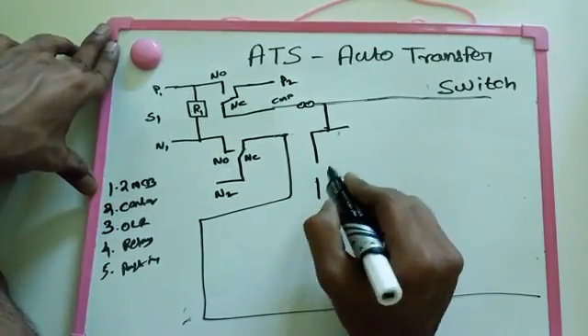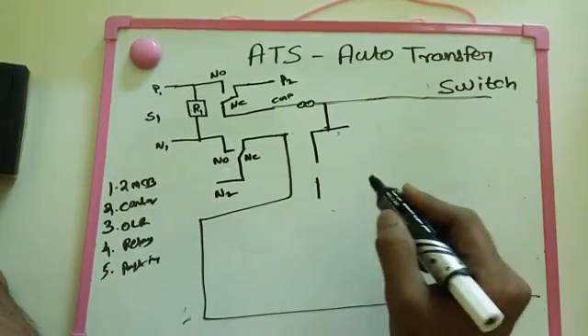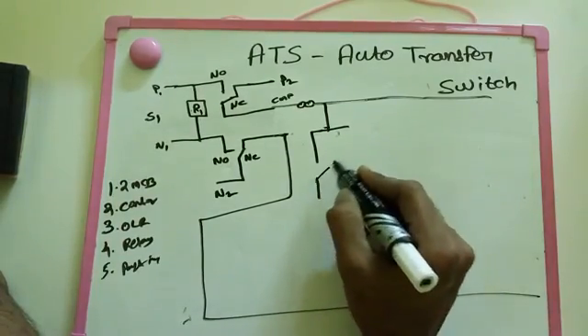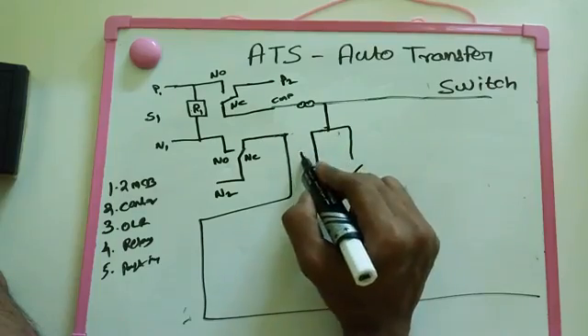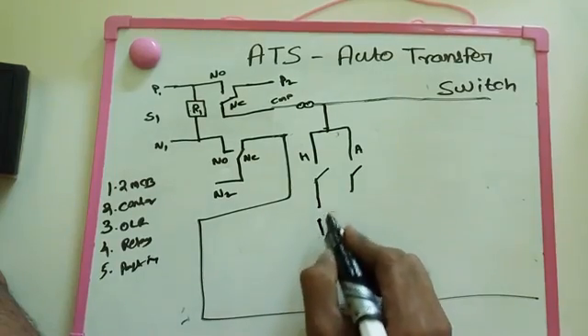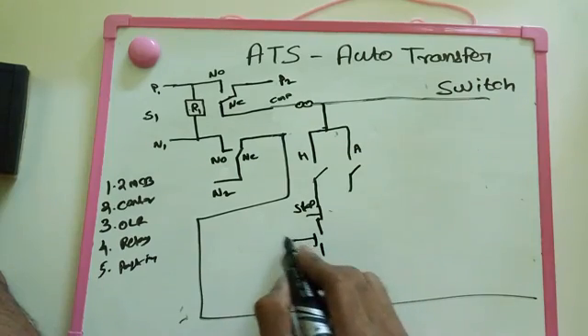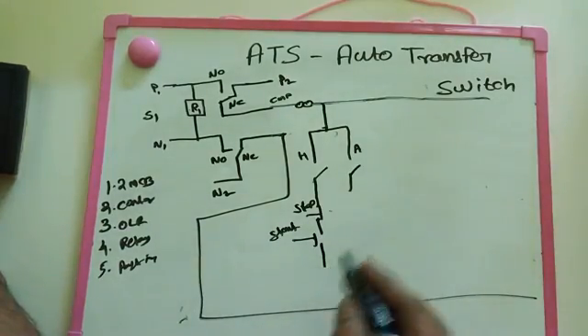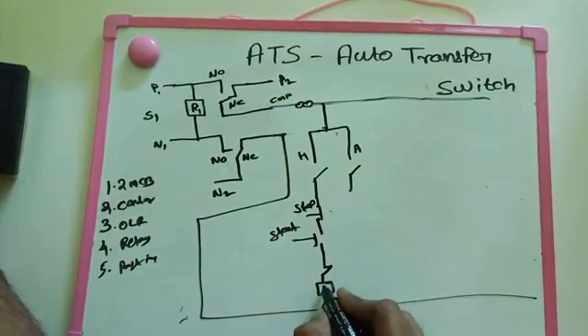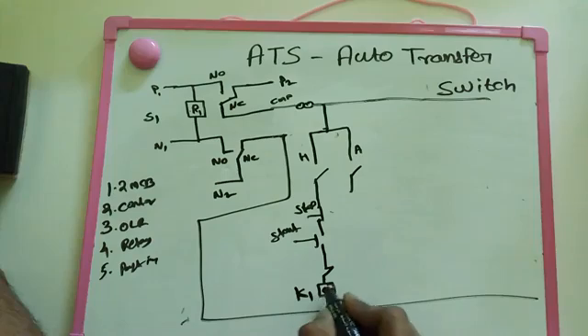First thing we need is hand-off and auto - that means we need hand operation and also auto operation. What is meant by hand and what is meant by auto? If the automatic has a problem - any maintenance issue or any problem with the automatic - at that time we need to maintain hand operation. So here this one is hand and this one is auto. We select using a selector switch. In hand mode, after that we make stop as normally closed and start as normally open. After that we need to interlock another system.